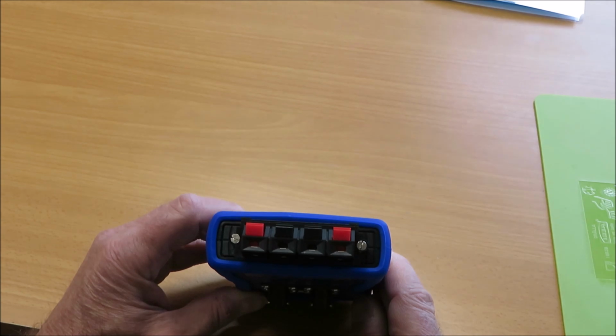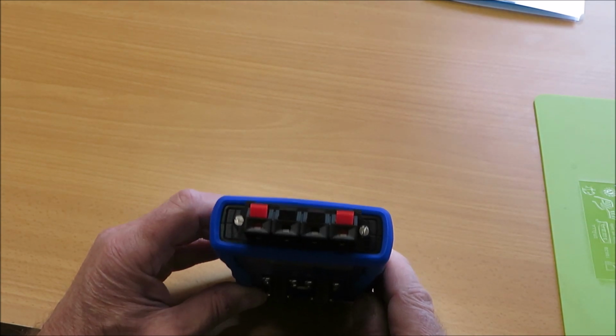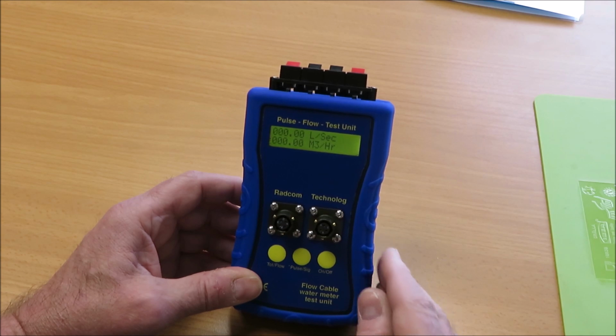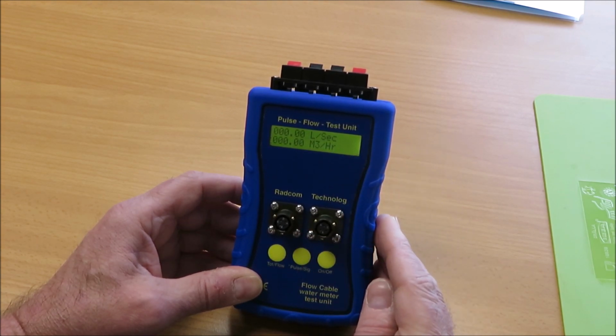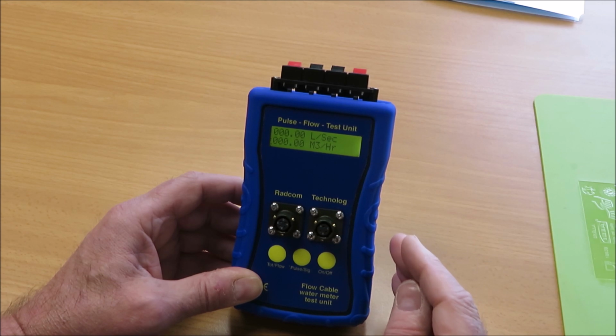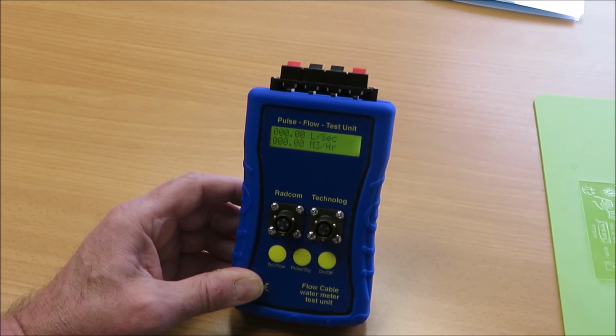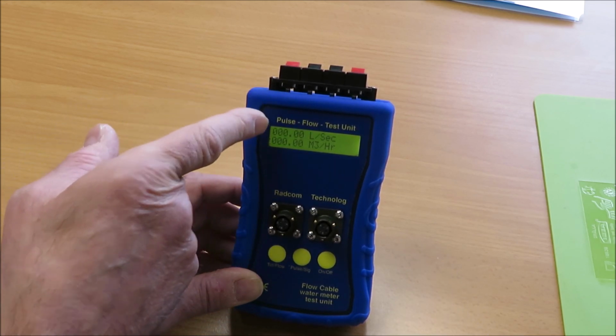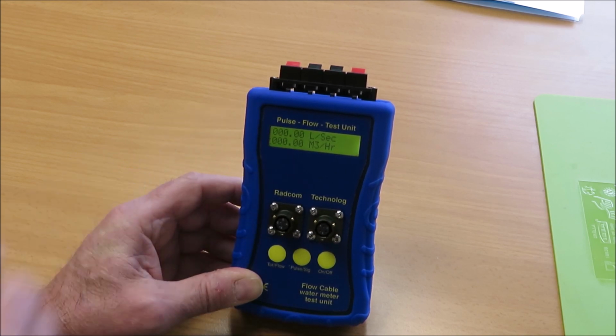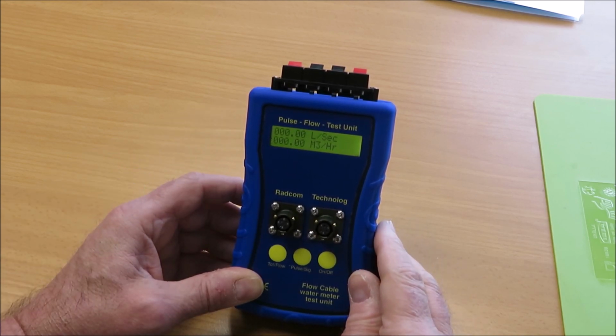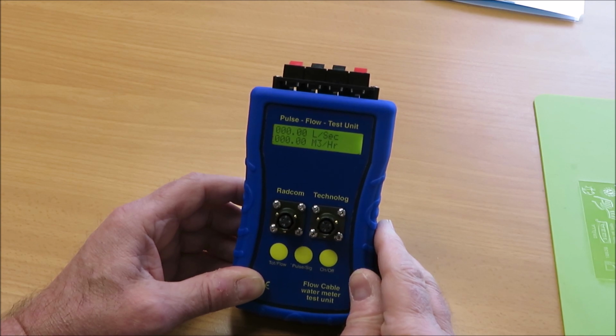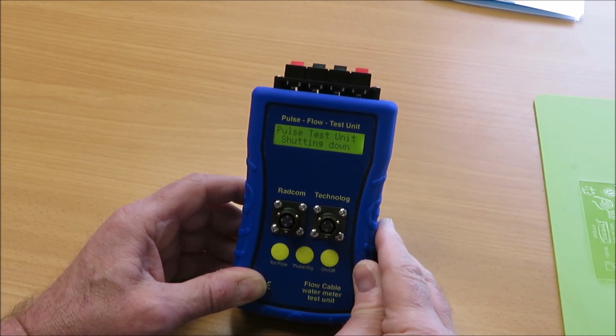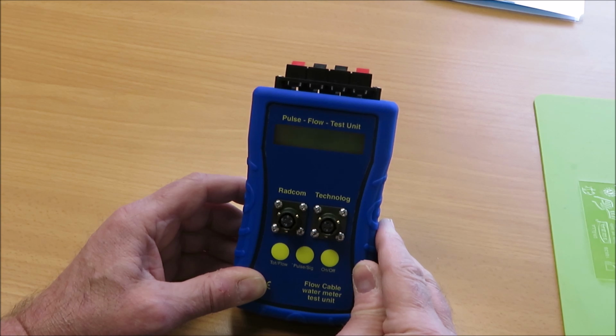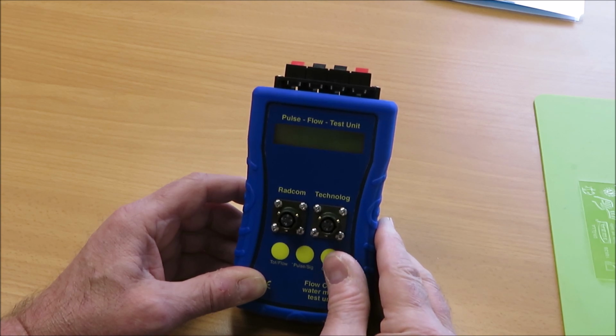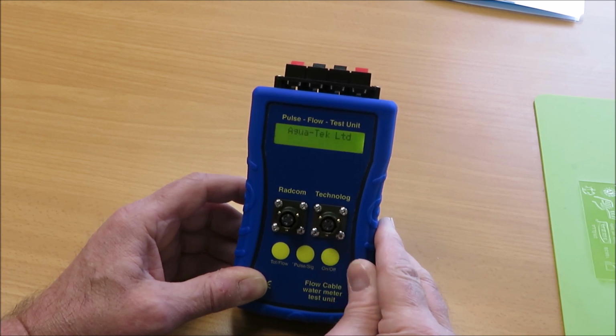And on the top you have the quick fit connectors, and the way to remember, the ones to the right that say test unit, below them, they're the flow input or pulse input connections, and the pulse output connections are on the left hand side here as indicated by pulse. The unit will switch itself off after approximately 30 minutes as standard, in which case it just shuts itself down to save the battery. This can be adjusted in a hidden menu, which is detailed in the manual.